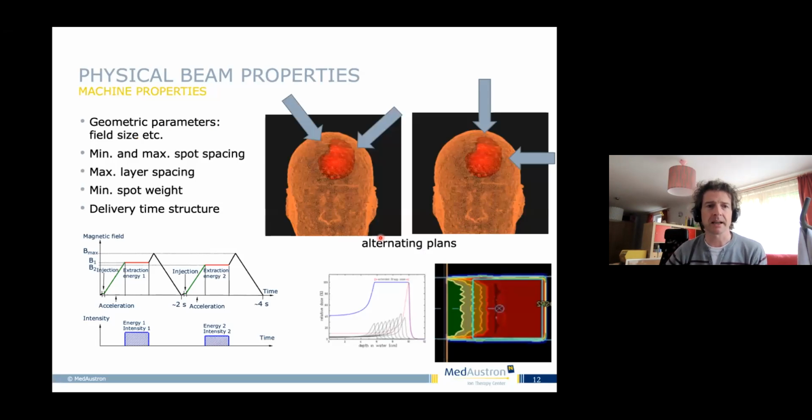Another aspect we have to have in mind is, Marco was addressing this before, CNAO is working on multi-energy extraction, similar to what MedAustron is doing, for a good reason. That treatment times with synchrotron technology, as implemented in the PIM study, are generating beam on times still exceeding the ones of cyclotrons, just by the fact that you need to have the cycle of extraction of energy, washing the magnets, injecting another time, and getting another energy out of the synchrotron. And by that, you have beam on times which are sometimes too long for clinical treatments in some indications.